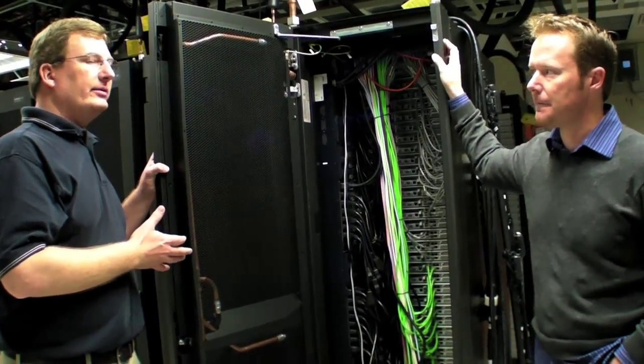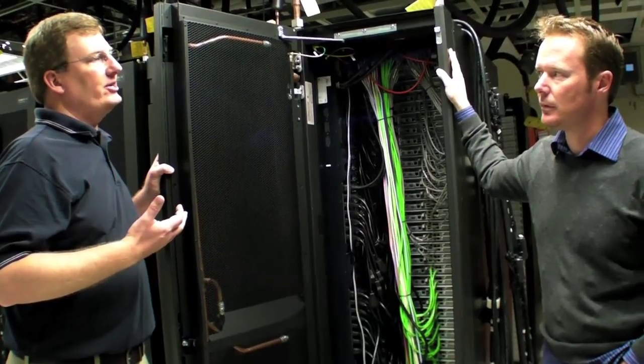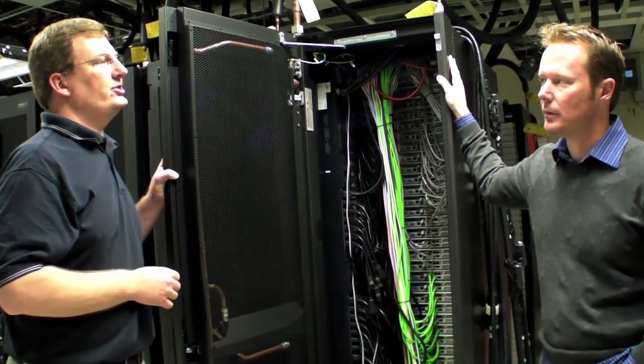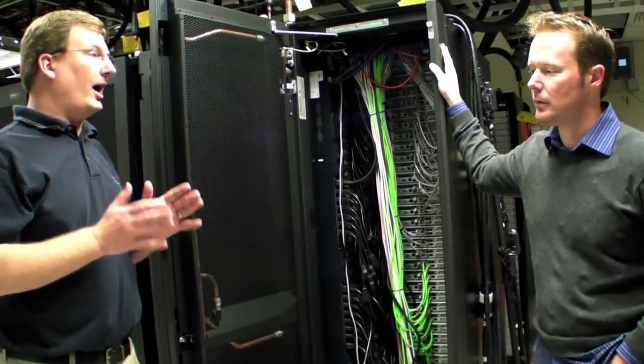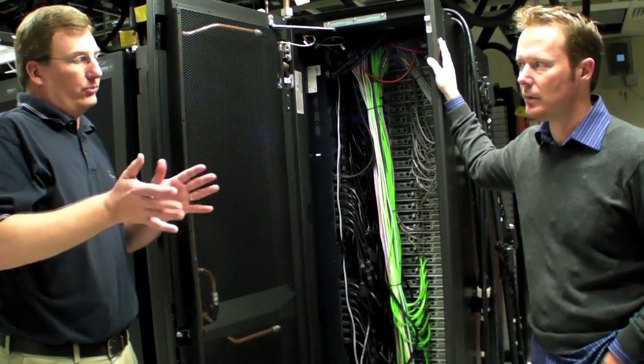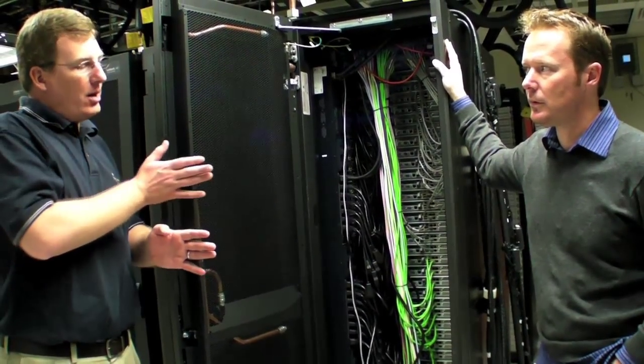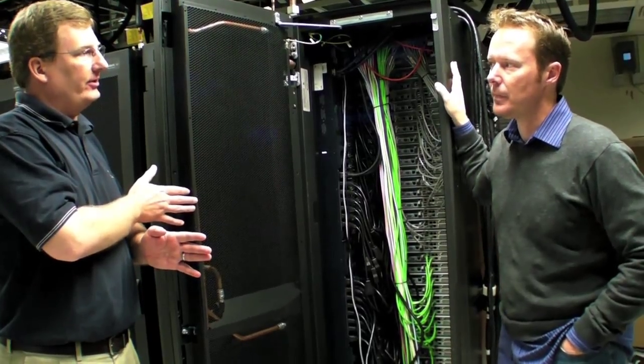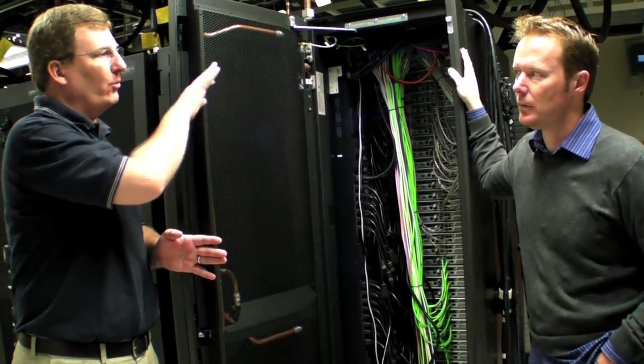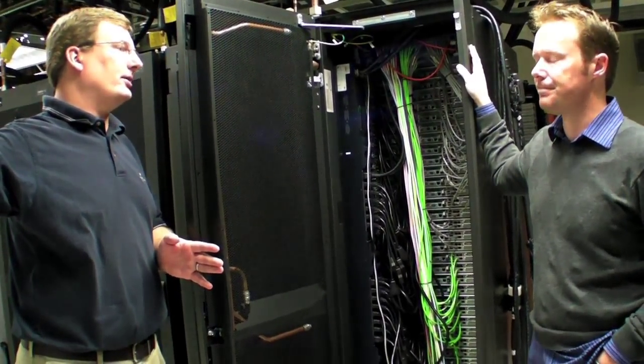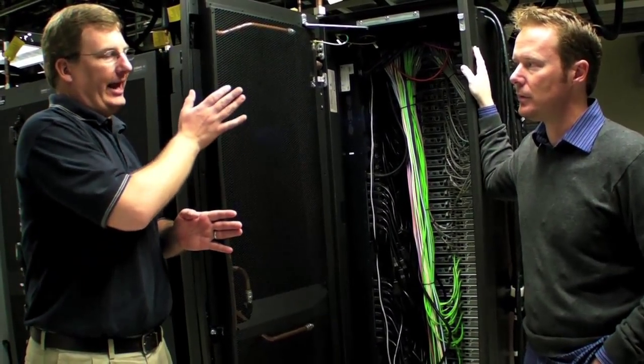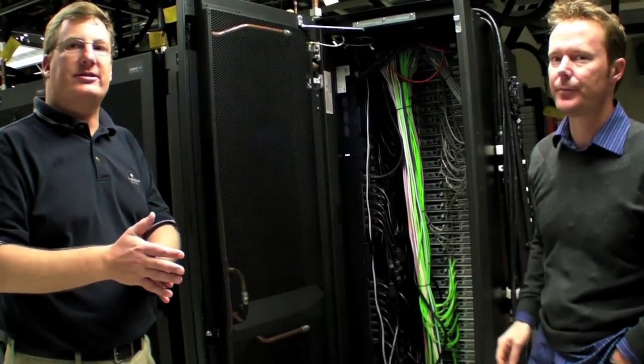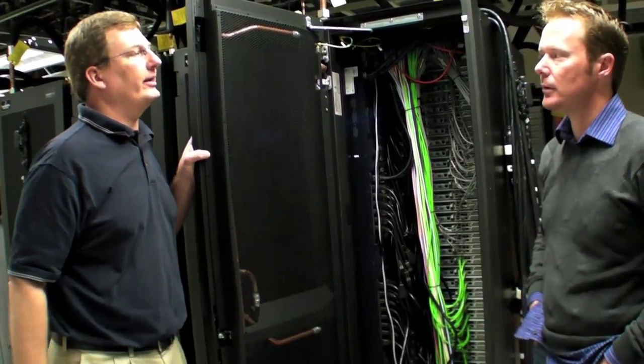The other nice thing is it opens up new configurations that might even be more energy efficient. We traditionally had hot aisle and cold aisle containment, or with or without containment. But now with this type of configuration, you can actually move the air straight across the data center, from one side to the other, where the exit of one rack becomes the entrance to the next rack. And that's something this product allows you to do.